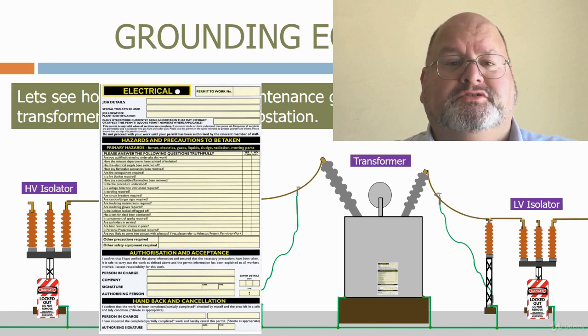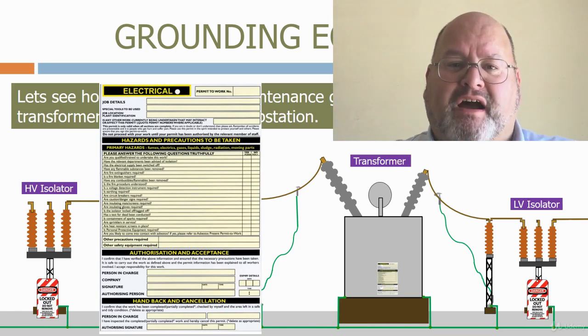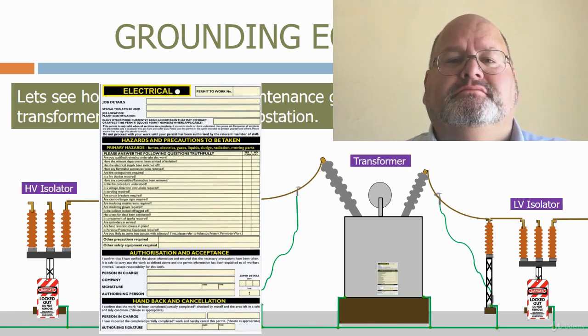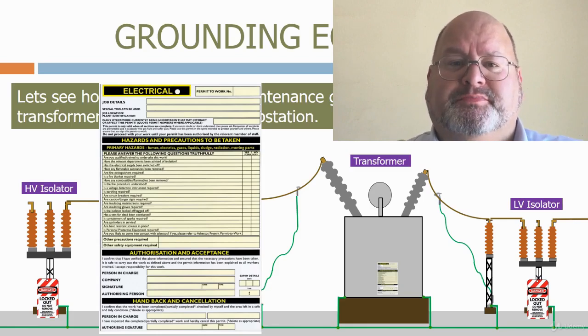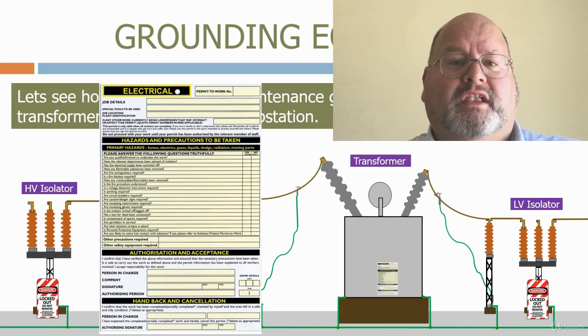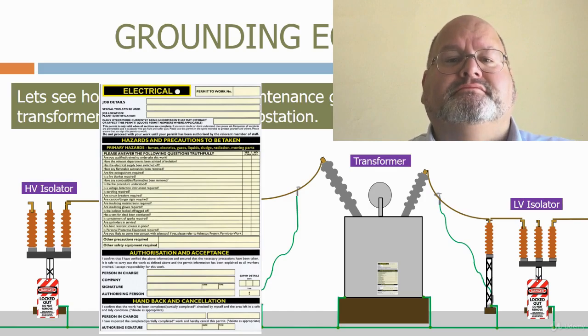Whenever a piece of line or busbar is being worked on, it has to be grounded before the work permit is issued. The grounding points should be between the source of the electrical energy and the area being worked on. Inside substations, ground spigots are provided for the connection of one end of the ground leads, which are then clamped onto the conductor being worked on using the insulated stick provided.